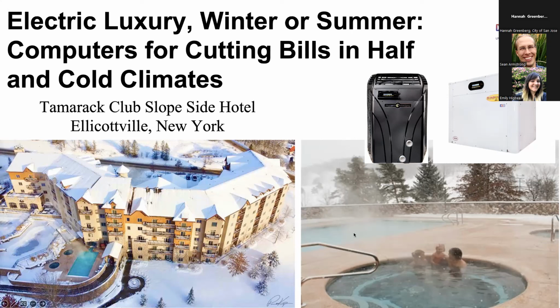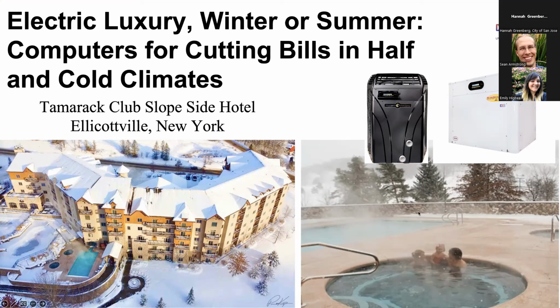They heat the swimming pool water with an air source heat pump, pulling heat from the air to about 80-85 degrees, then take extra heat from it and put it into the hot tubs to make them 105-110 degrees. The whole system is designed so all three get heated—it's actually a water source heat pump, collecting heat from the swimming pool and putting it into the hot tubs. This lowered their bills in half.